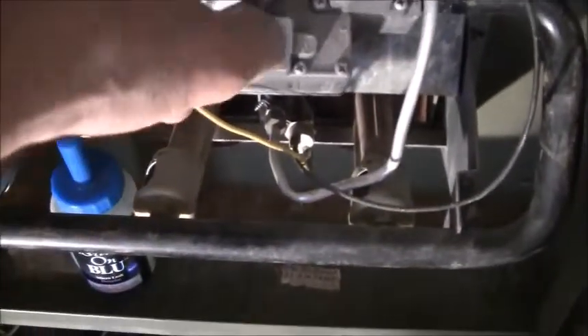The way that you do that on this valve is there's a spring here. You have to bring that back and then turn this to off that way. Then I'm going to take this valve, turn that to on, which is in line with the pipe, that's on. Now this line here is pressurized. The joint that I disturbed is pressurized.